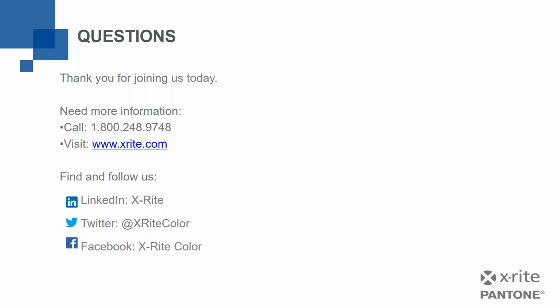Somebody else asked a question about the benefit of profiling versus yearly calibration. So there's benefits to both. Yearly calibration, of course, ensures that we are functional in a controlled environment to very, very accurate standards. Yearly certification or yearly calibration at X-Rite also includes the instrument being cleaned. It includes a new calibration tile for your device and those kinds of things. So there's some other benefits.